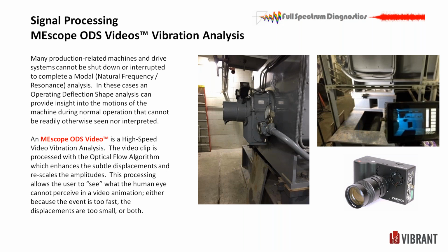Hello, everybody. Thanks for coming out today. I know everybody's probably getting sick of webinars, but we have one that's a little more fun than the other ones out there. We're going to look at a piece of equipment that I did a test on a couple of weeks ago. It was a turbine generator system, direct driven through a gearbox. What you're looking at on the screen in the middle picture is the outboard bearing of the generator. And the picture just to the right of that is the foundation of the generator foot. And the little blue image in here is the Chronos 1.4 camera, which is right there. So kind of a peek into how we did the survey and so forth.